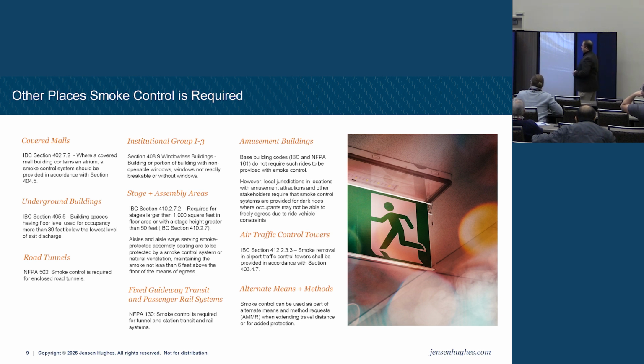Fixed guideway transit, so passenger rail systems, amusement buildings. So this one is very common. Big theme parks, even if it's not required to be there, if they're low light or limited egress or a challenging environment where there's a lot of special effects, they may mandate smoke control anyway, right? Even if it's not a code requirement, it's kind of above and beyond. If they're using theatrical smokes, if you are intentionally kept in the dark for whatever reason, right? It's excitement factor or whatever, often smoke control is required. And that can be by state to state and by theme park to theme park. Like Disney has their own code requirements for about everything they do.